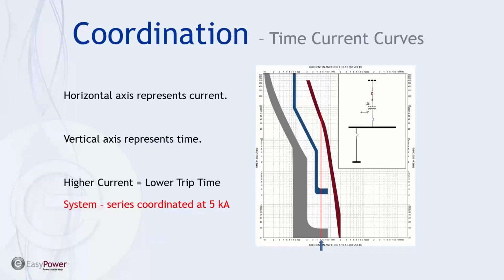So for instance, at 5,000 amps, it looks like the molded case circuit breaker would trip in 20 milliseconds. If that didn't clear, then a low voltage power circuit breaker will trip in 300 milliseconds. And then finally, if neither of those cleared, then the primary fusing looks like it would clear in about 80 seconds. And again, its primary function is to prevent a fire, usually in the transformer. It's relatively easy to make the statement that at 5,000 amps, this system is series coordinated.